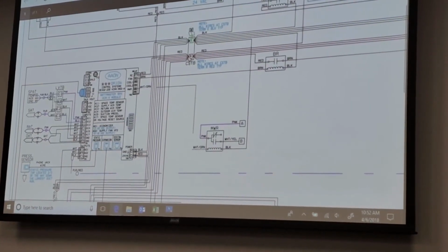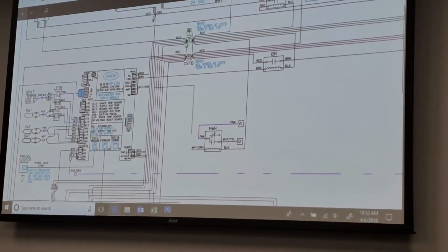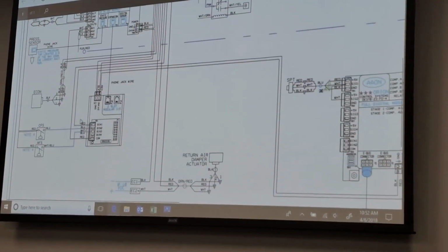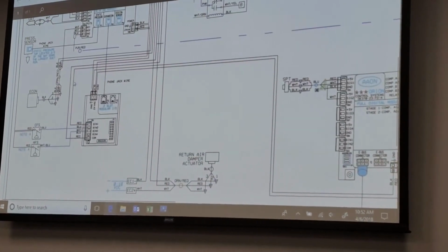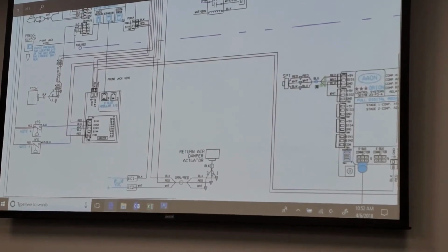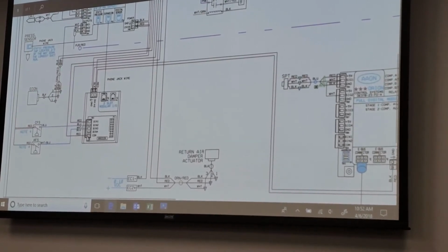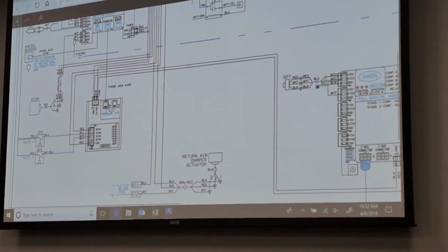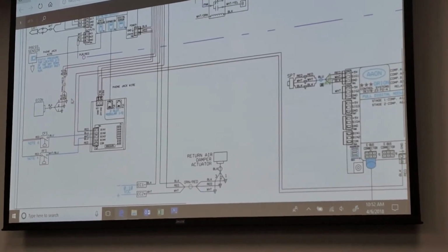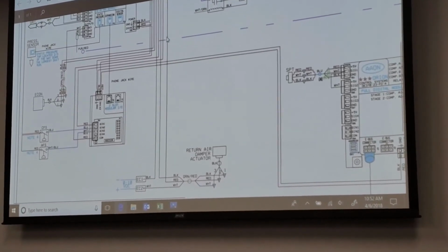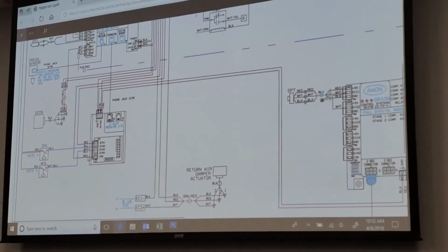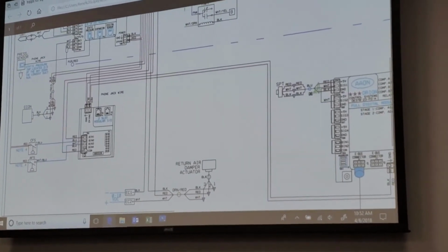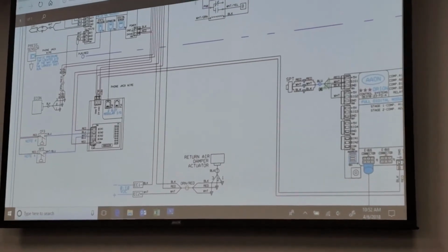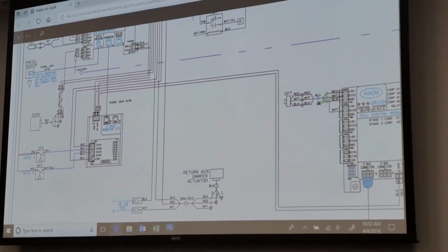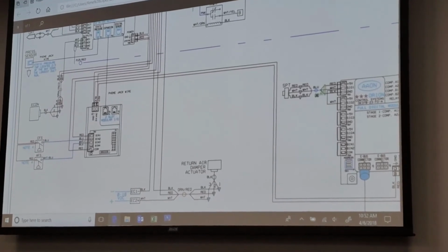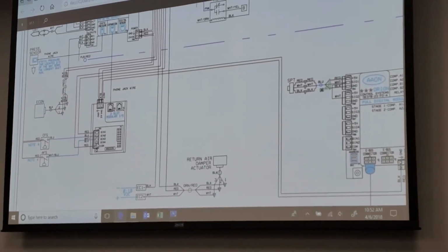24 volt power right here. Black is your common. They actually have a red wire coming down right into the common. That common should actually be a black wire. That should have been a black wire going up to the common side of that 24 volts. And all they did is create a direct short and blew that board up. That's how it came from the factory. There's the wiring diagram from the factory. Wrong. It should be a black wire.